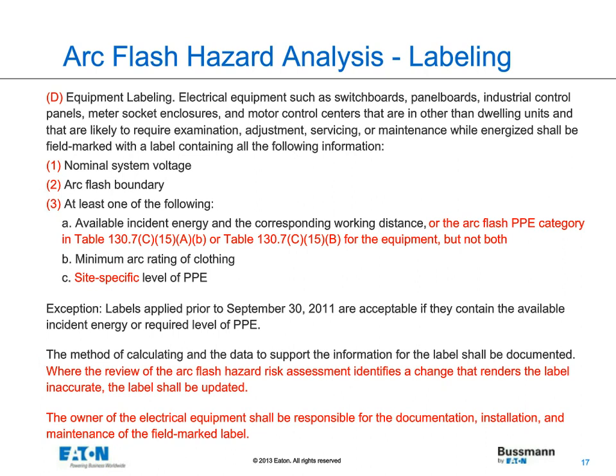If you look further on in 130.5(D), we've added some additional text: where the review of the arc flash hazard assessment identifies a change that makes the label inaccurate, the label shall be updated. That corresponds with the five-year period we should review, and if we find it needs to be updated, we must do that. The last sentence added says the responsibility for documentation, installation, and maintenance of the field-marked label is solely the owner of the facility. So that is my last slide that I'm covering today.